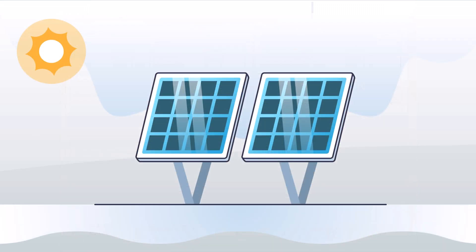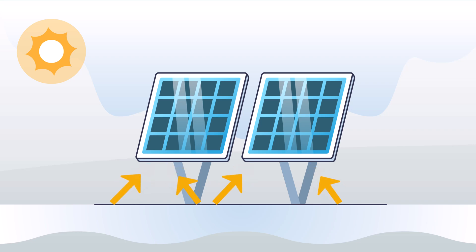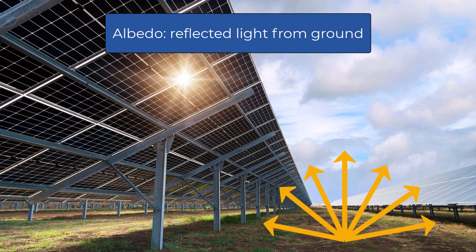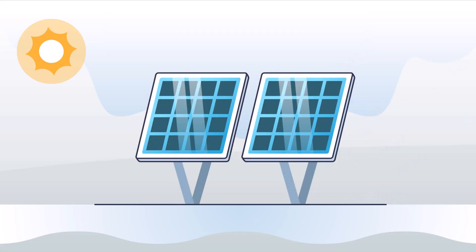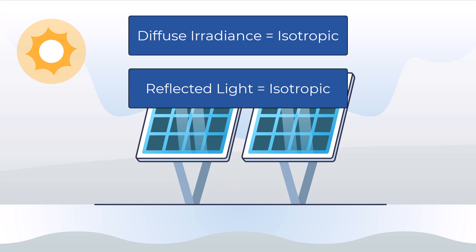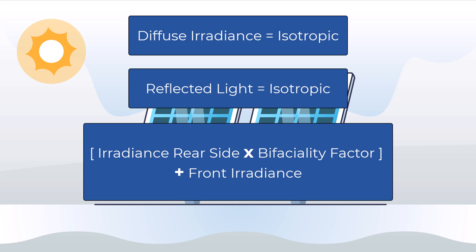In most cases, the usable irradiance at the rear side is mainly the reflection of some parts of the incident light on the ground, which is named albedo. The main hypotheses for the bifacial model in PVSYST are: the diffuse irradiance is isotropic, and the reflected light at each point of the ground is isotropic with a specified albedo factor. The additional irradiance on the rear side is multiplied by the bifaciality factor and then added to the front irradiance for application on the one diode model.